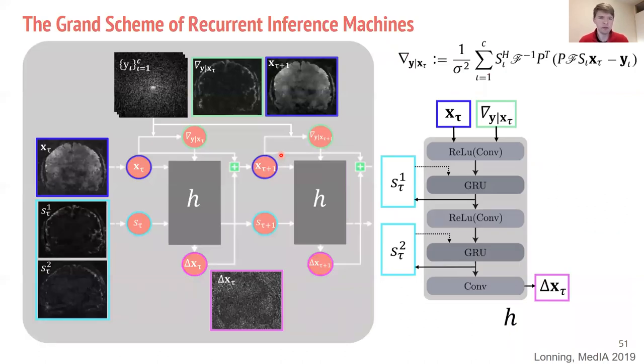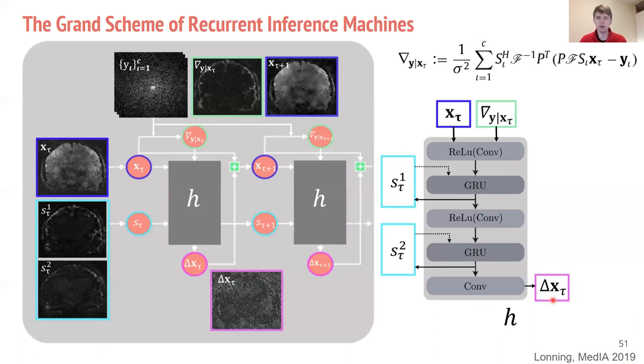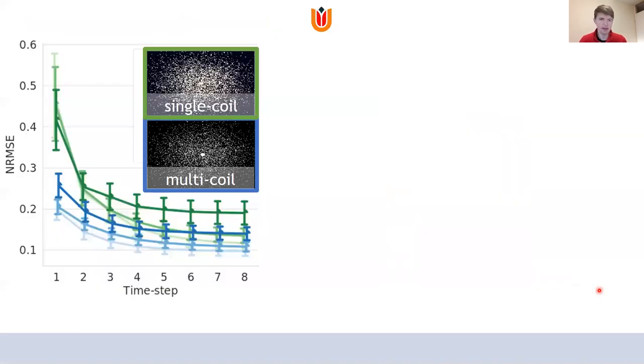The network takes an iterative approach with parameters shared over iterations. Per iteration, the current estimate of the image is given along with the log likelihood gradients — this is where the forward model with the MR physics is embedded in the network. Passing through the network yields an update delta-x which is added to the current image estimate. This recurrent approach is beneficial because the error reduces over iterations until convergence; we chose eight time steps before terminating the reconstruction.